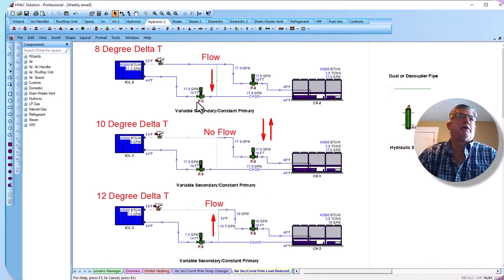So obviously there's a lower flow at each one of these pumps, right? And then there's going to be a greater flow on the bypass. I come back here and go by there. You'll see there's 3 GPM there as opposed to the 10 that was being bypassed before.